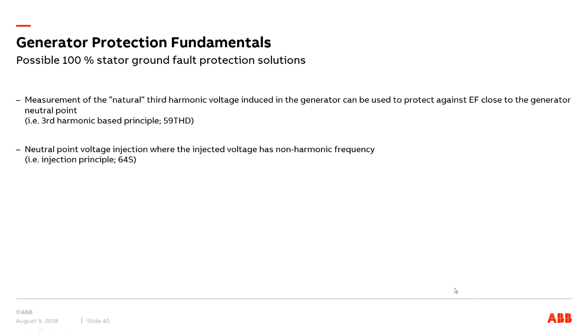The generator will not generate a pure sinusoidal wave, as stator windings are not perfectly shaped to give this perfect voltage. The generator will give a certain degree of harmonics in the power generator. The third harmonic voltage generated has the characteristics of a zero sequence voltage. This means that there will be a third harmonic voltage in the generator neutral during normal operation. In case of a ground fault close to the neutral, this third harmonic voltage will be reduced and can therefore be an indication of a fault.